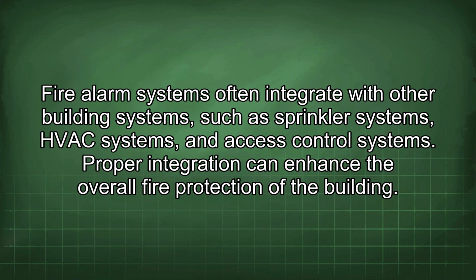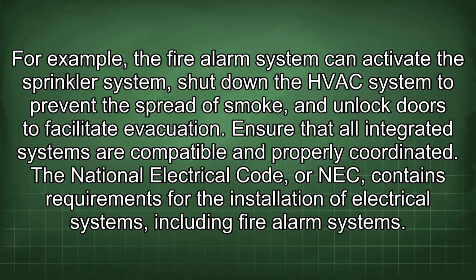Fire alarm systems often integrate with other building systems such as sprinkler systems, HVAC systems, and access control systems. Proper integration can enhance the overall fire protection of the building. For example, the fire alarm system can activate the sprinkler system, shut down the HVAC system to prevent the spread of smoke, and unlock doors to facilitate evacuation. Ensure that all integrated systems are compatible and properly coordinated.